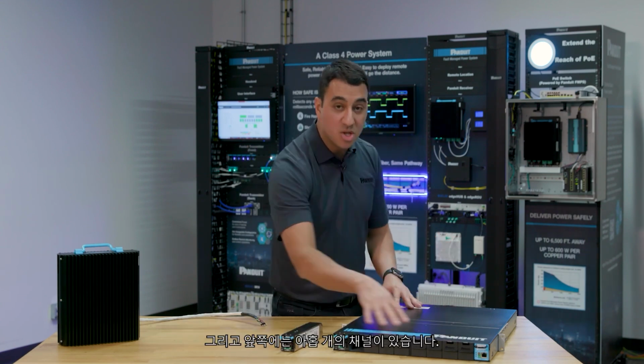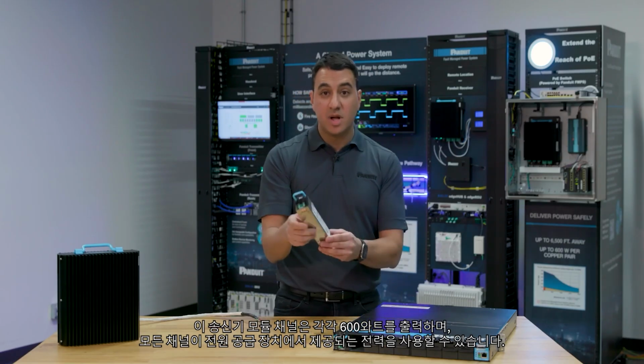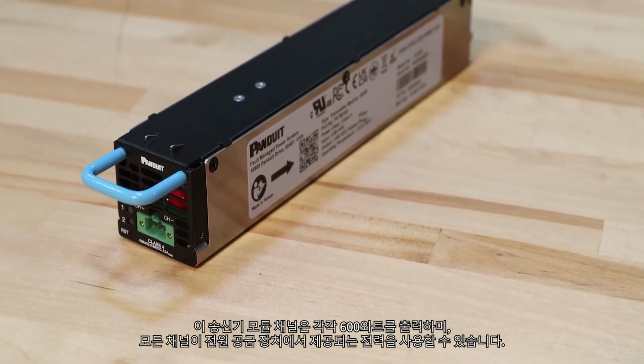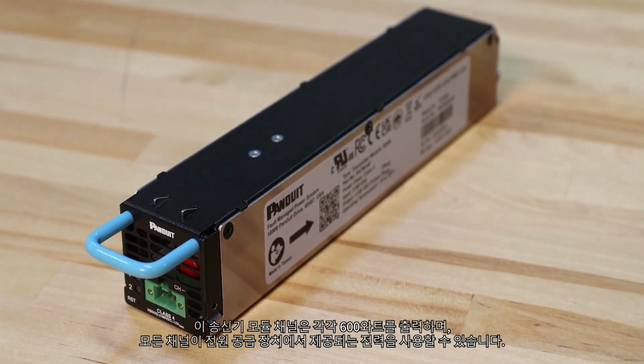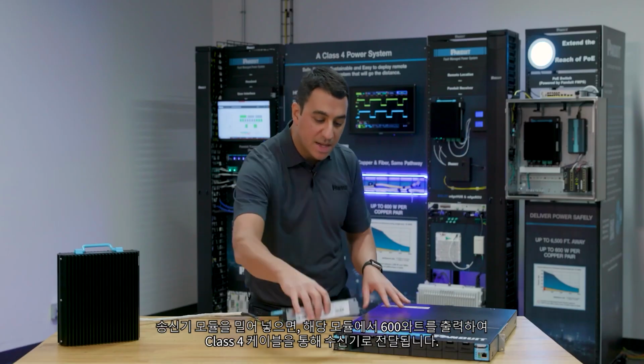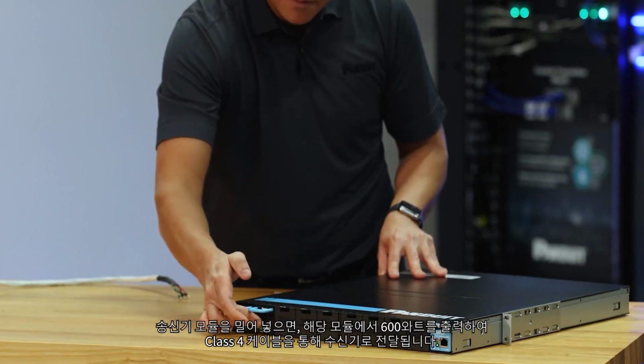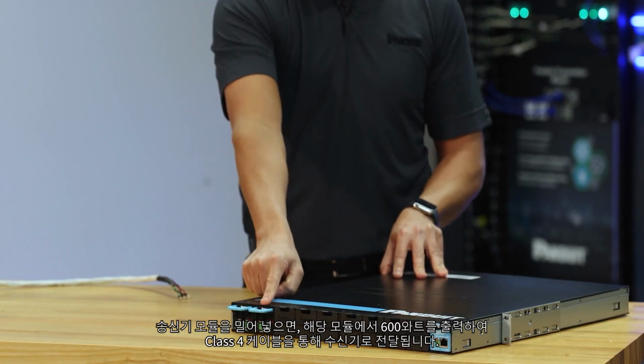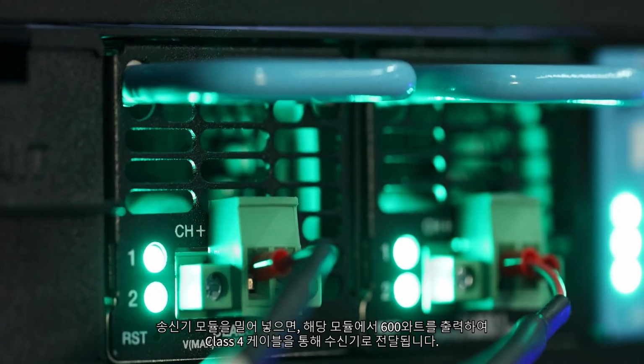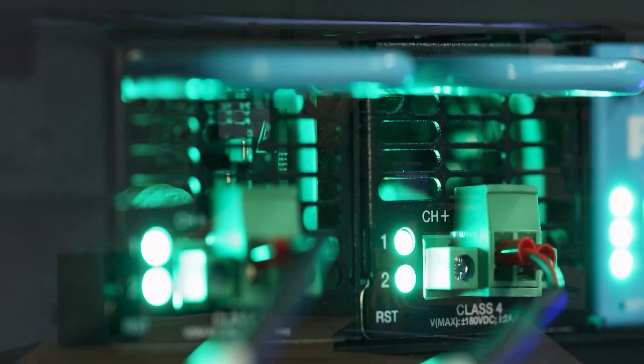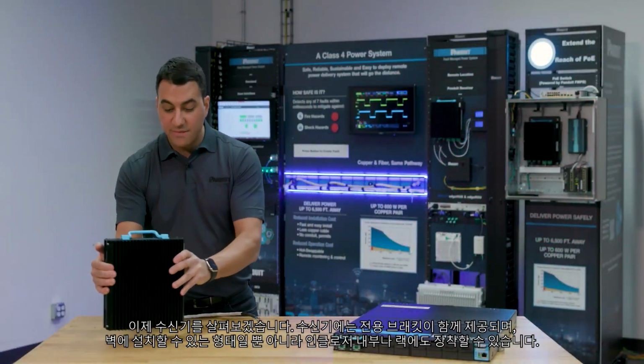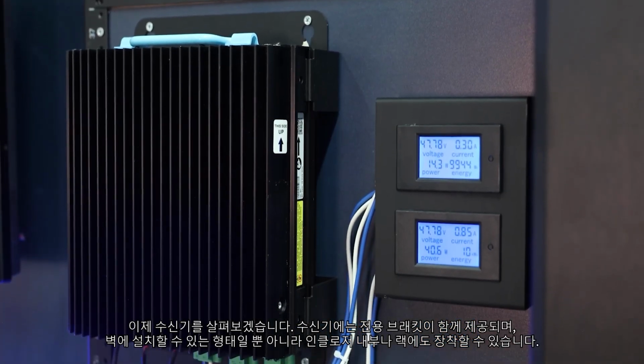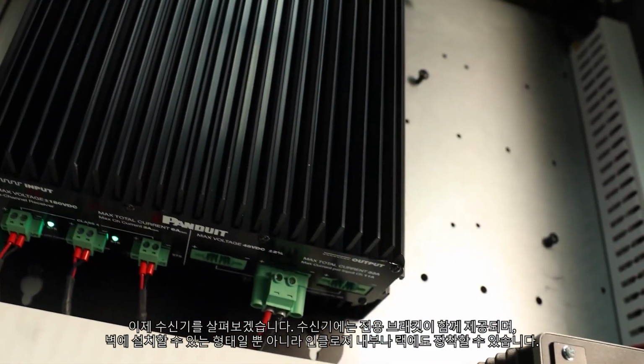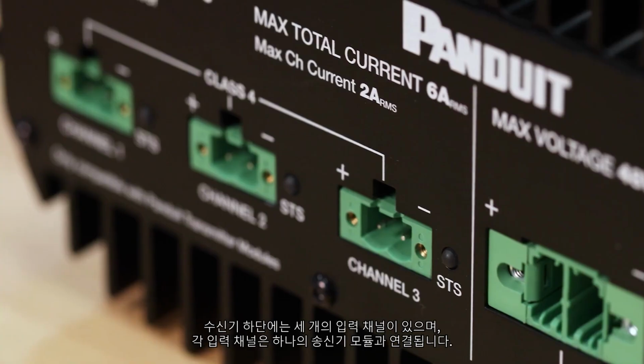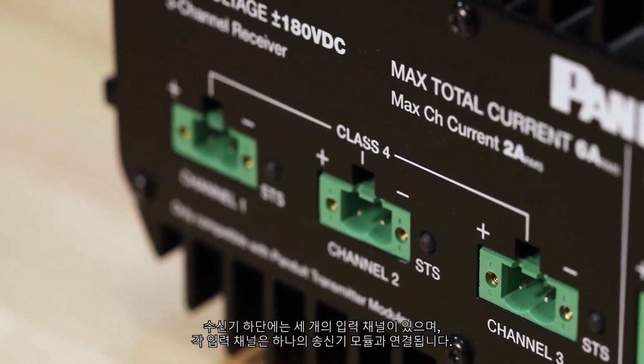In the front, I mentioned 9 channels. Each one of these transmitter module channels outputs 600 watts. And they all have access to the power being supplied by the power supply units. You simply slide in a transmitter module, and now you can have 600 watts out of the transmitter module, and it goes out through Class 4 cable to the receiver. Now let's talk about the receiver. The receiver comes with its own bracket, and it's a wall mount unit, or could also be mounted inside an enclosure or on a rack. It has 3 input channels on the bottom. Each input channel connects to a single transmitter module.